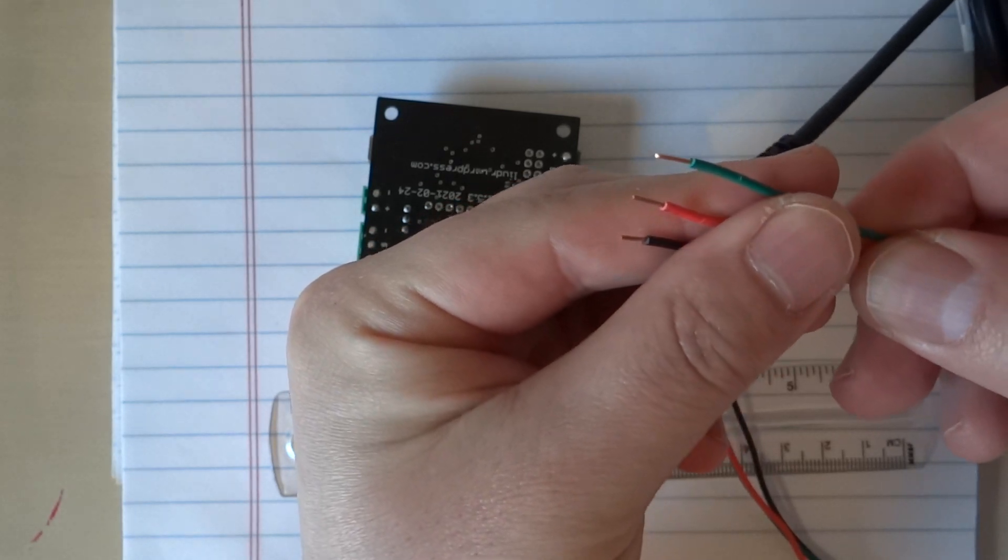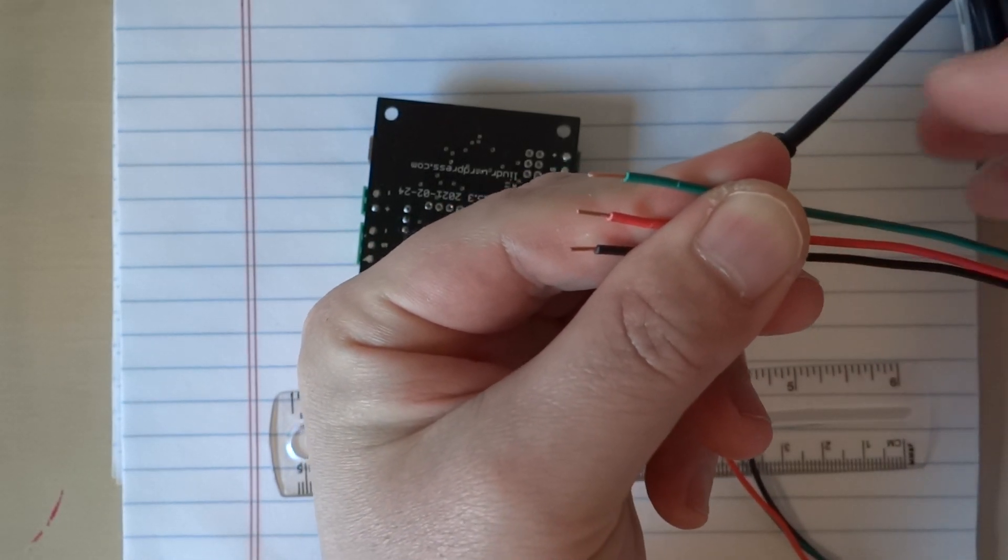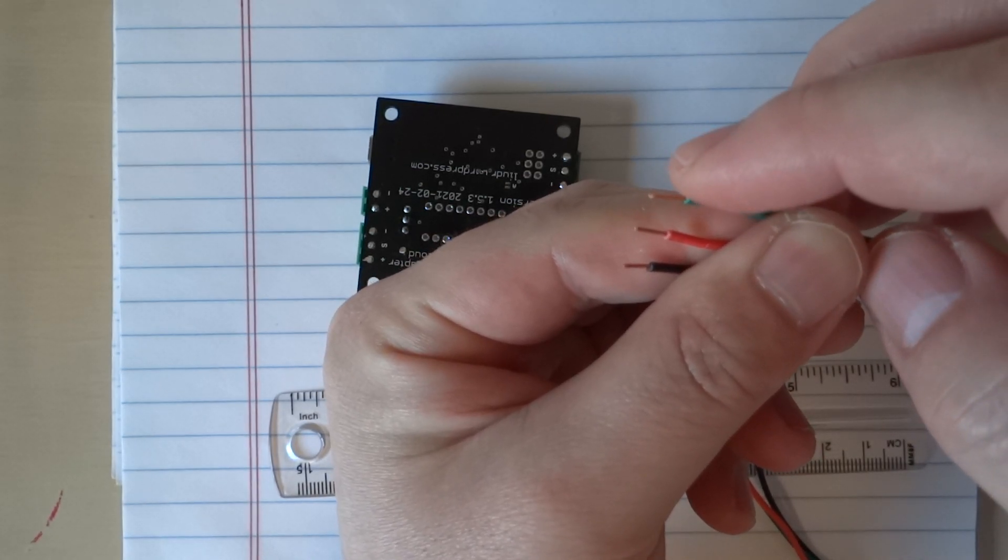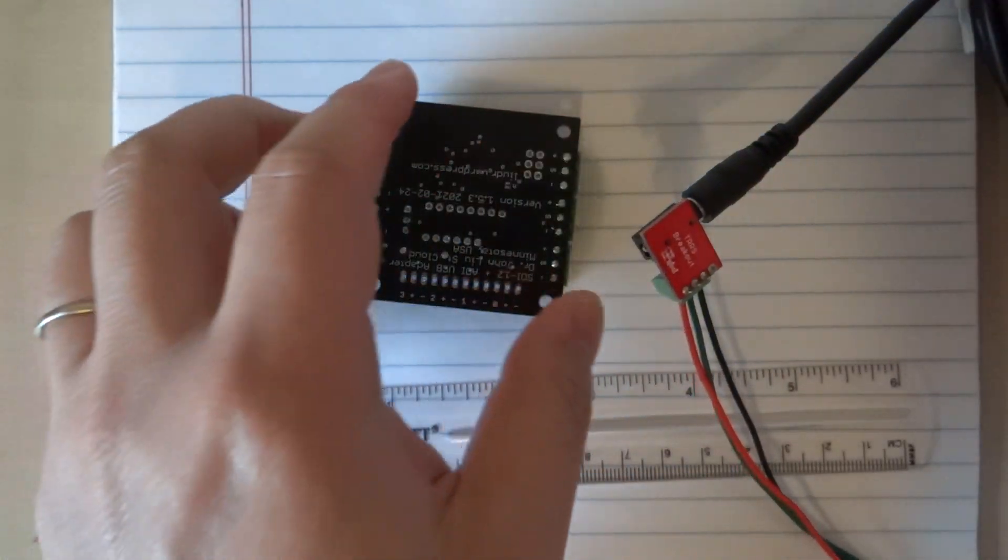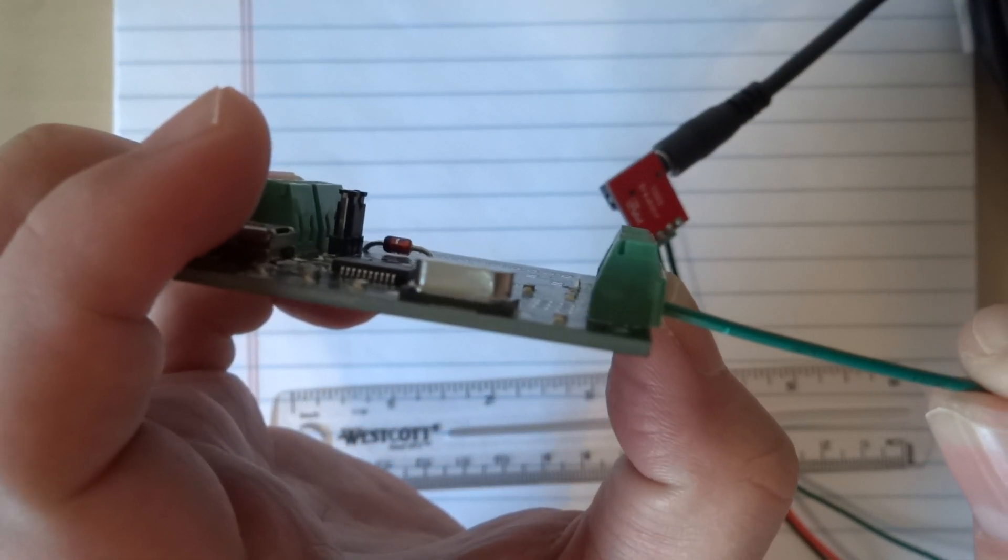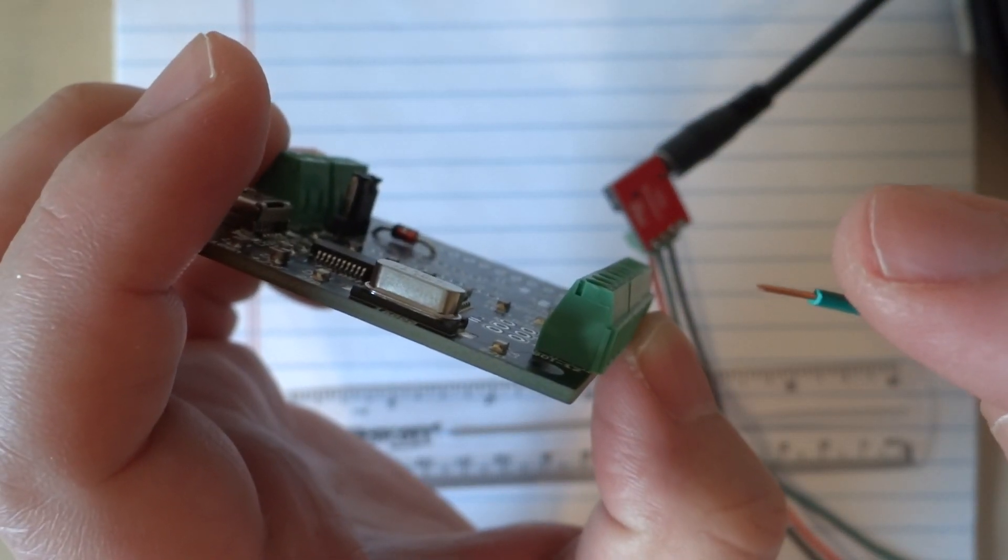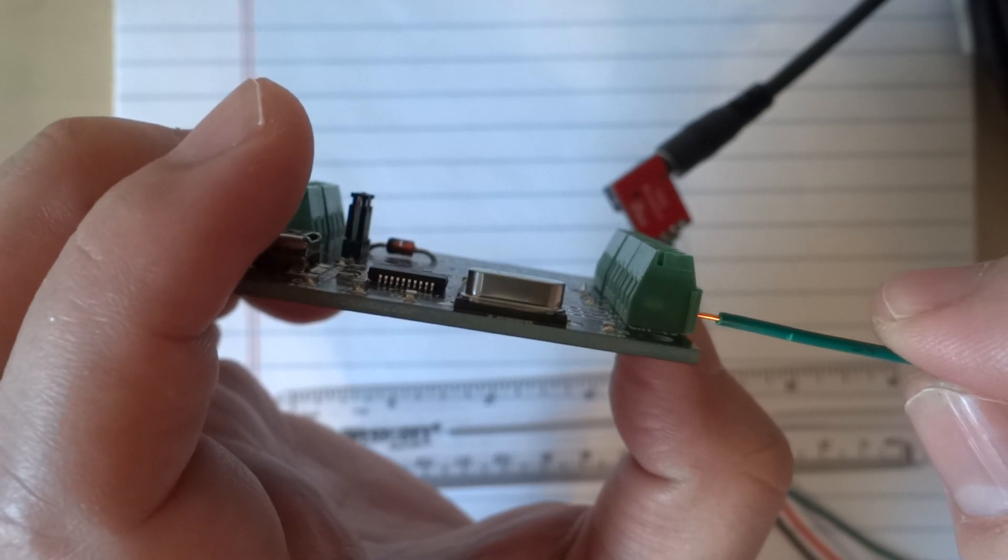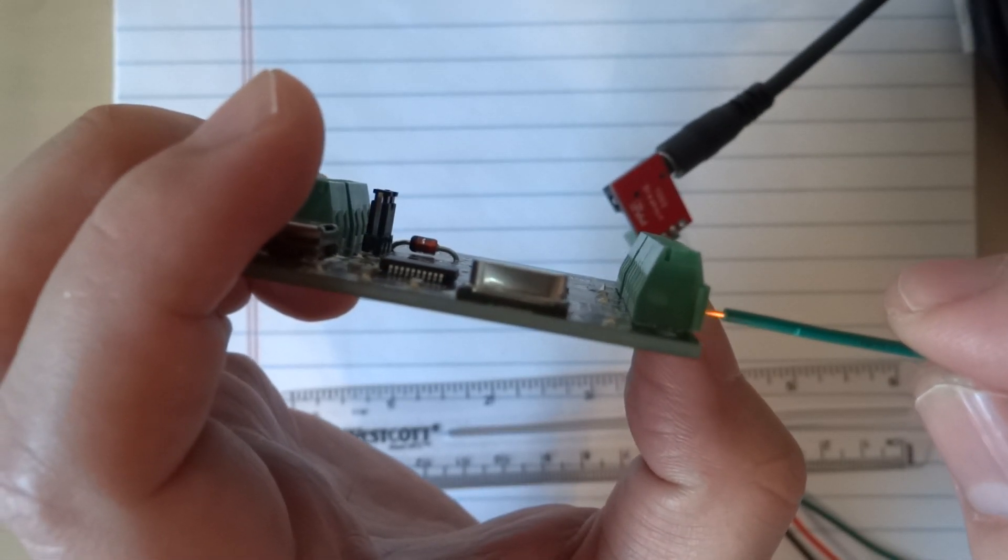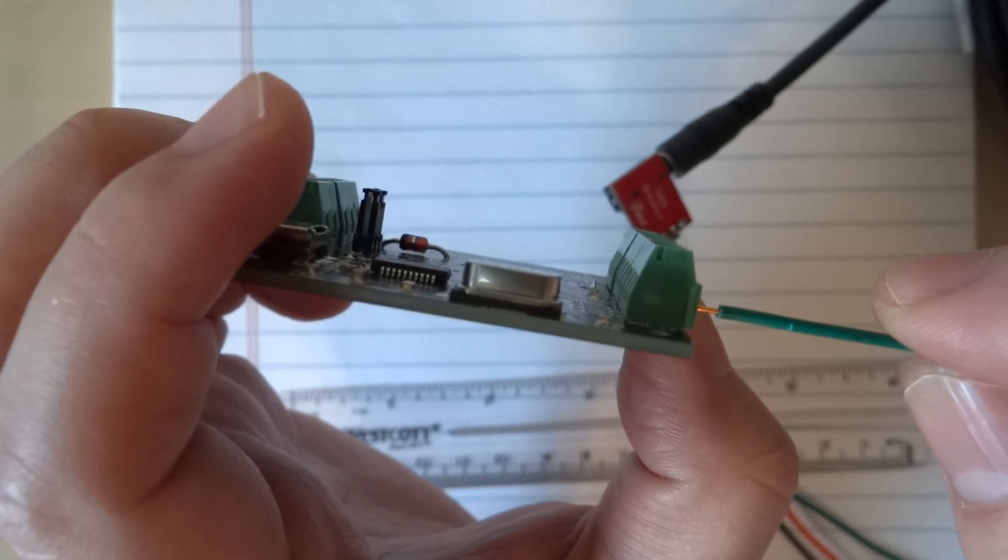Before you wire these into the terminal blocks, just make sure you don't trim the wires too long. This is roughly the length I recommend. If you cut this too long, then there will be a certain amount of bare conductor left outside, and that's just inviting a short circuit with the neighbors—that's not good.